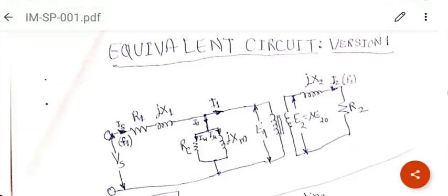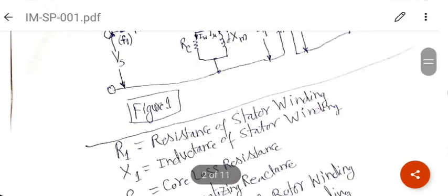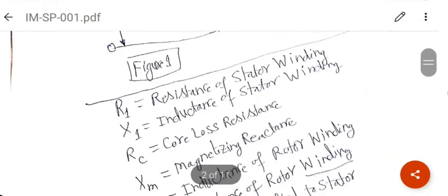Okay. Now this is the equivalent circuit. The secondary side current, of course, is being called I2, and there is no voltage because it's all short circuited anyway. And secondary side resistance, that means rotor winding resistance, is R2, and inductance in the rotor is L2, and correspondingly we will see a reactance X2. Unfortunately, X2 will depend on F2, and F2 is a variable with slip, so that has to be captured in interpreting the equivalent circuit.